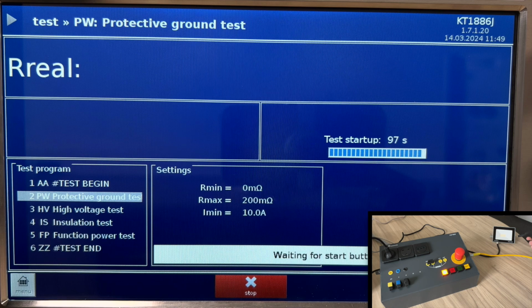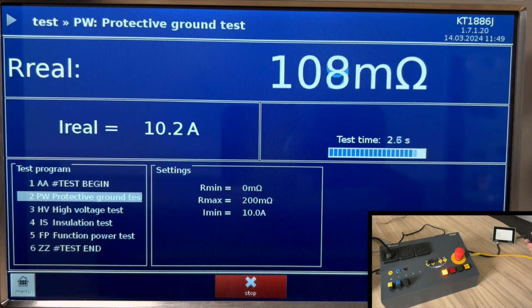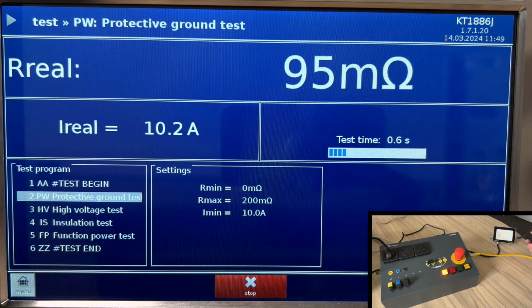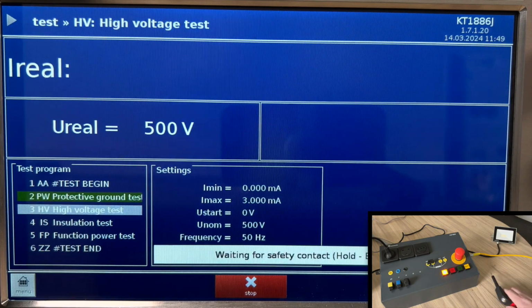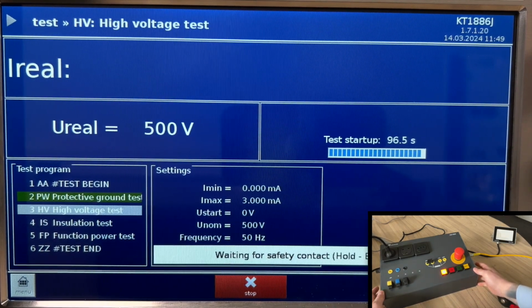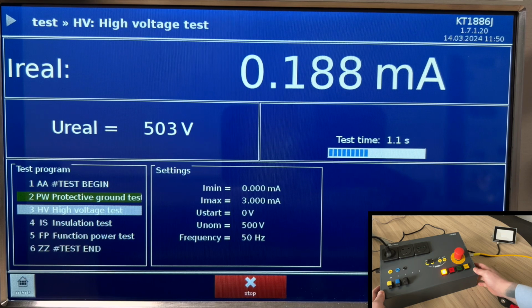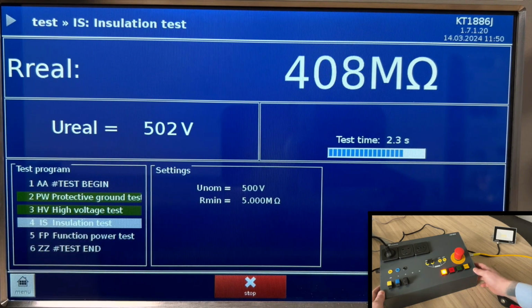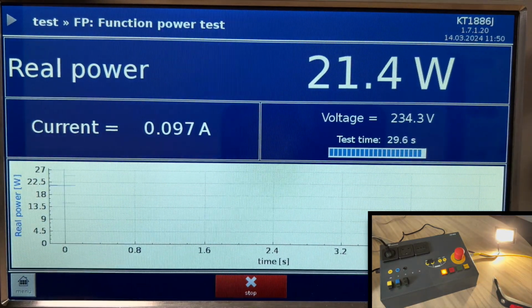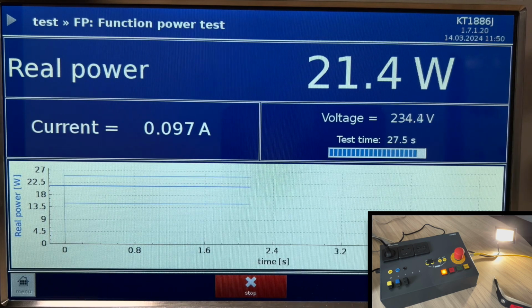The first step, we will start with start button on eProbe for protective ground test. For high voltage, we will use the two-hand safety control on the panel. The same will be for insulation test. And the last one is function power test, where we can see our DUT light up.